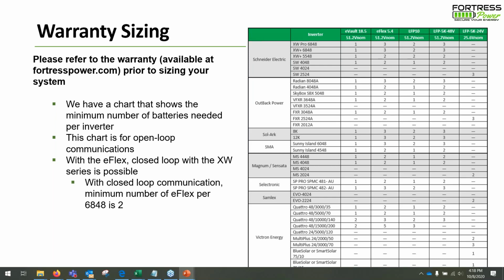most systems are. If you look at the 6848 and the XW Plus and the XW Pro, the minimum number of LFP10s is 2, for exactly the same reasons that I explained before, the sizing calculations. And you'll see that the minimum number of Eflexes is 3. Now, this is true for open loop communications because of the calculations that we made before. But with closed loop communication, the minimum number of Eflexes per XW Pro and XW Plus is 2. Now I'll explain why here.